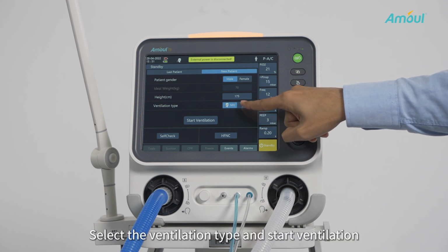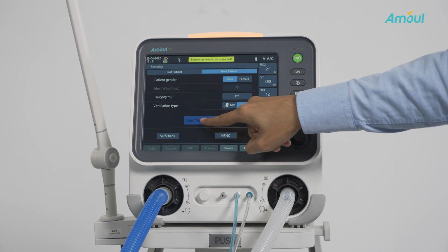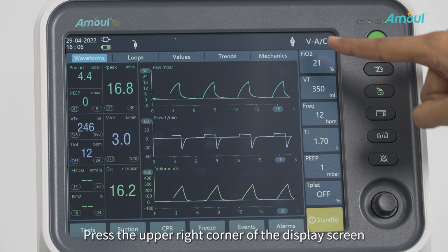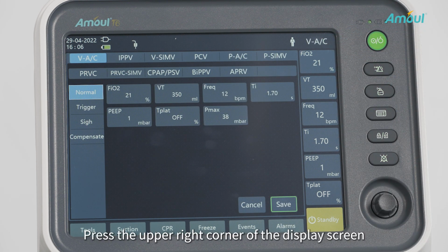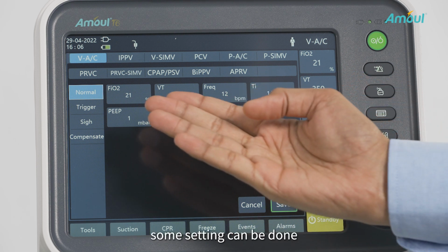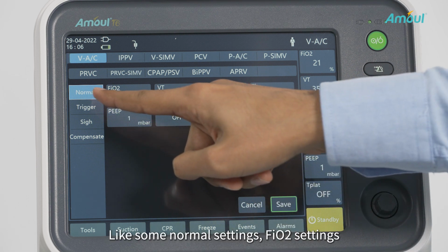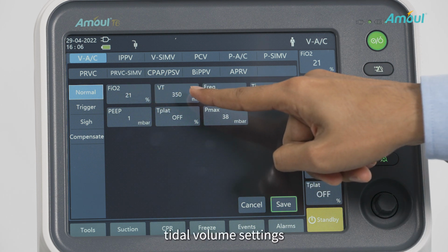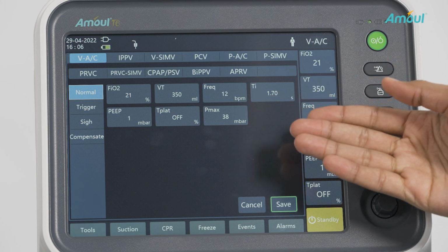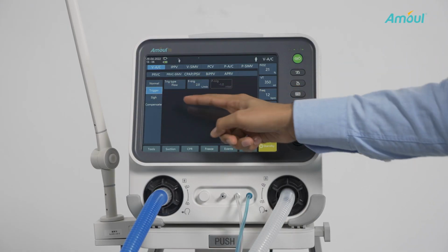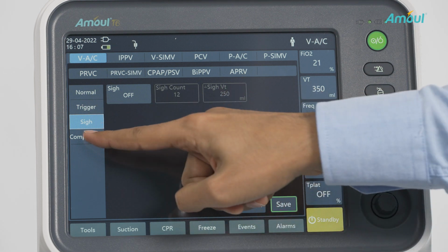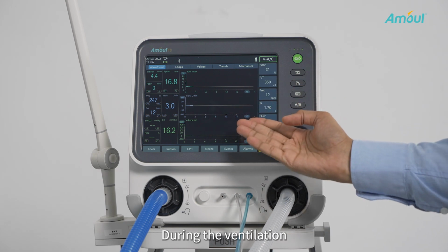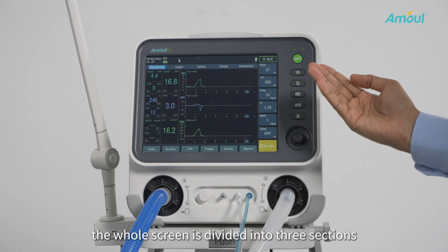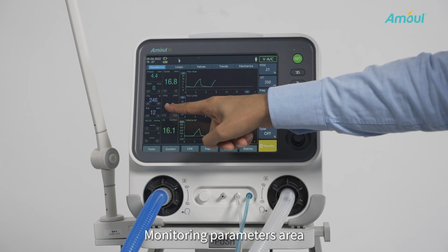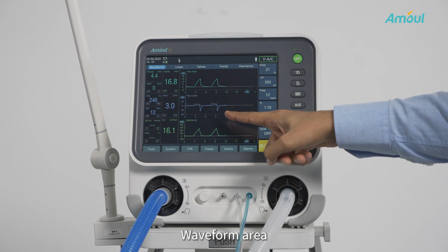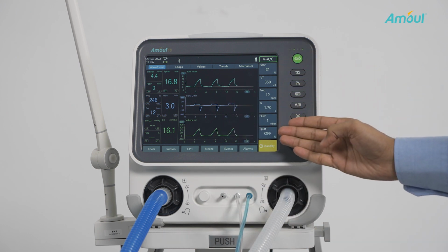Select the ventilation type and start ventilation. To select the desired ventilation mode, press the upper right corner of the display screen. After selecting the desired ventilation mode, some settings can be done, like some normal settings, FiO2 settings, tidal volume settings, frequency settings, etc., as well as trigger settings, sigh settings, and compensate settings. During the ventilation, the whole screen is divided into 3 sections: monitoring parameters area, waveform area, and setting parameters area.